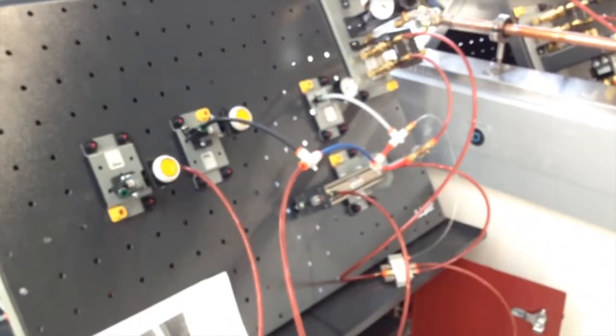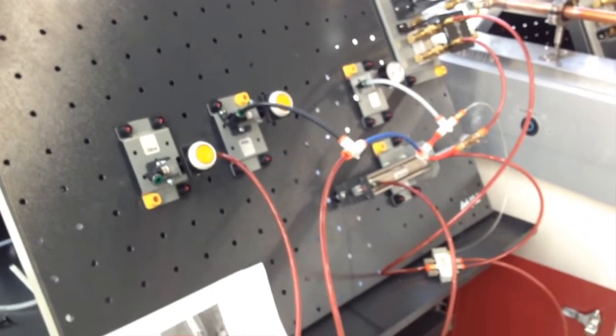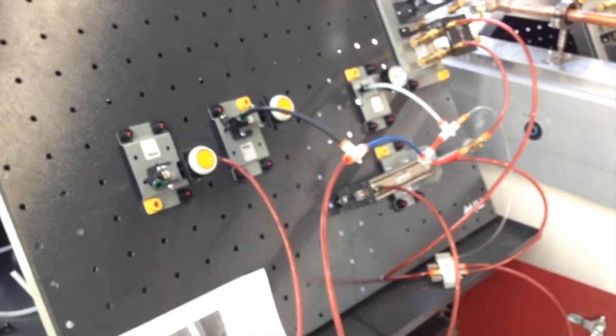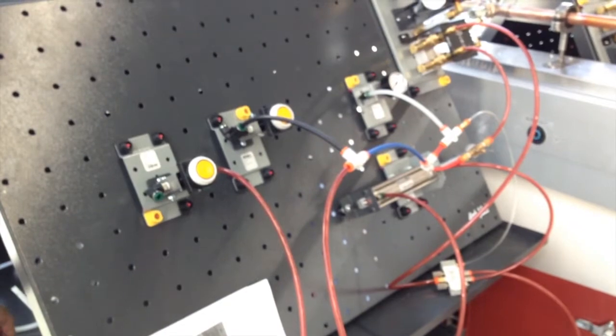Close too tight, it's going to take a long time to retract the cylinder. Opened up too much, it's going to waste a lot when any one of the buttons is depressed. Button bleed circuit.